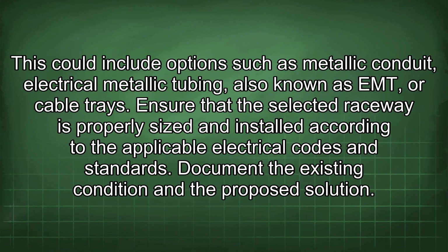Provide the contractor with details of appropriate raceways that meet applicable codes and standards. This could include options such as metallic conduit, electrical metallic tubing, also known as EMT, or cable trays. Ensure that the selected raceway is properly sized and installed according to the applicable electrical codes and standards.